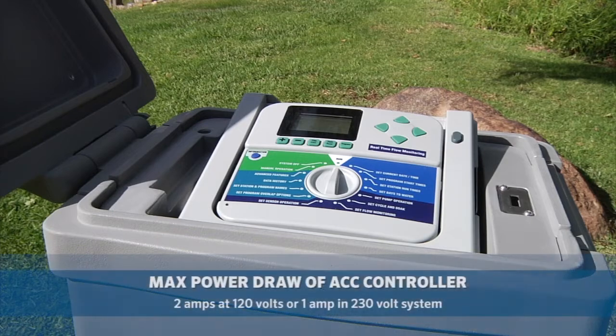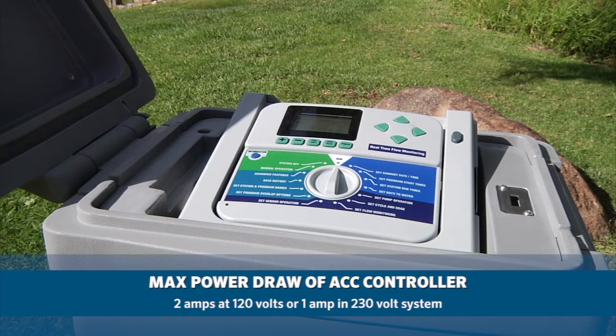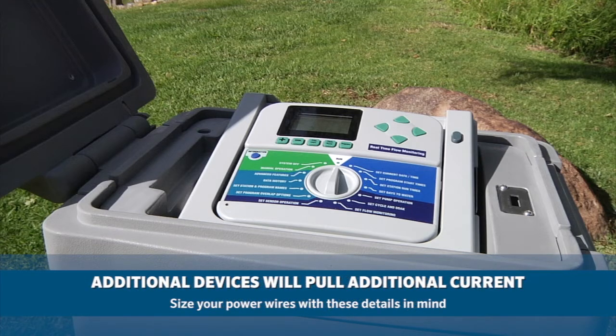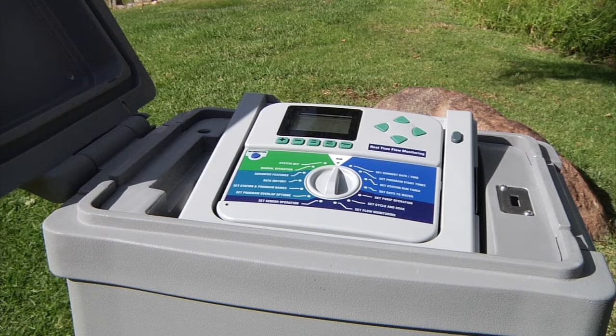The maximum power draw of an ACC controller by itself is 2 amps at 120 volts, or 1 amp in the 230 volt applications. Additional devices on the power line will pull additional current, so size your power wires with these details in mind.